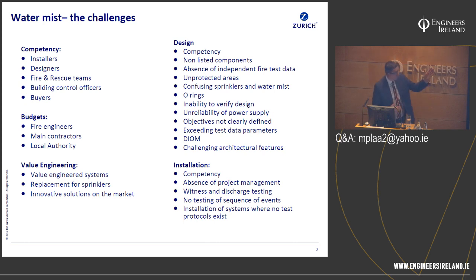And there's a big long list here of design issues that we come across. And I think one of the biggest issues that I find and troubles me personally is the use of non-listed components. We still have some suppliers of water mist systems installing today in 2018 non-listed, non-third-party accredited components. This wouldn't happen in the sprinkler market. You'd have an LPCB, FM, UL listed sprinkler head. But that doesn't always happen in the water mist market. There are some very good manufacturers who supply third-party accredited components. It doesn't always apply to everybody in the field.